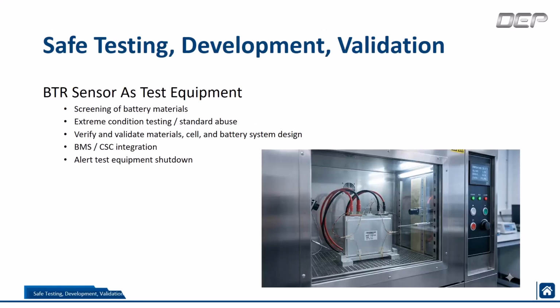So outside of battery storage systems, our sensor can also be used as test equipment. You can use this sensor for screening of battery materials. You can use it for extreme condition testing and standard abuse, as I've just shown. You can use it to verify and validate materials, cell, and battery system design. It can be integrated with the BMS and the CSC systems. And you can actually integrate it into an alert for a test equipment shutdown.